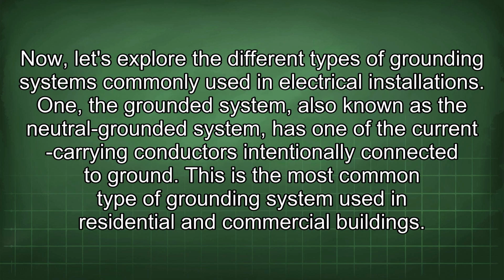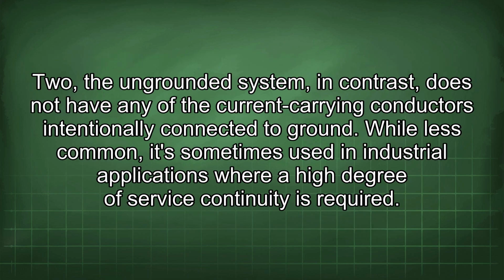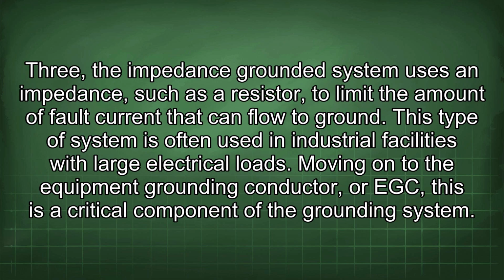Now let's explore the different types of grounding systems commonly used in electrical installations. 1. The grounded system, also known as the neutral grounded system, has one of the current carrying conductors intentionally connected to ground. This is the most common type of grounding system used in residential and commercial buildings. 2. The ungrounded system, in contrast, does not have any of the current carrying conductors intentionally connected to ground. While less common, it's sometimes used in industrial applications where a high degree of service continuity is required. 3. The impedance grounded system uses an impedance such as a resistor to limit the amount of fault current that can flow to ground. This type of system is often used in industrial facilities with large electrical loads.